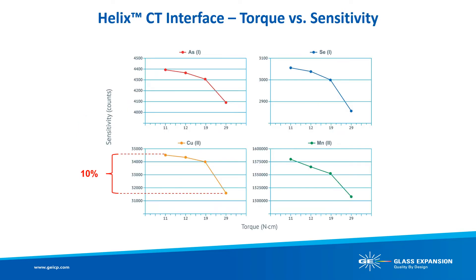Why is constant torque an important feature of Glass Expansion spray chambers? ICP sensitivity is affected by both nebulizer depth within the spray chamber and the torque applied to the nebulizer seal. Data highlights the effects of torque applied to the nebulizer seal versus observed sensitivity: as applied torque was increased incrementally, sensitivity decreased on average by 5%, with the greatest difference being 10%. The new Helix CT locking screw is set to the optimum torque, sealing the press-fit PTFE ferrule to the same torque each day, allowing the analyst to achieve the same nebulizer performance every day.